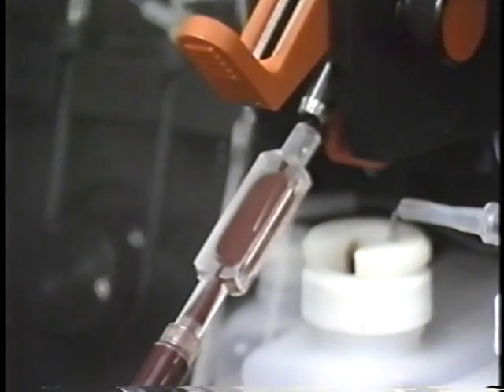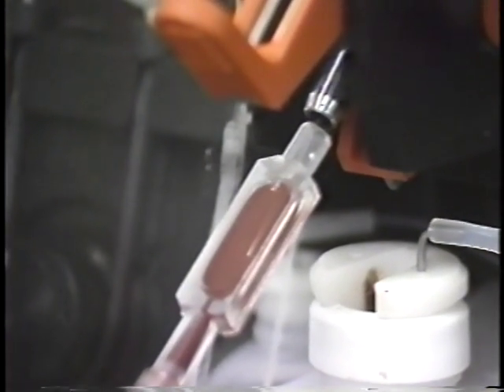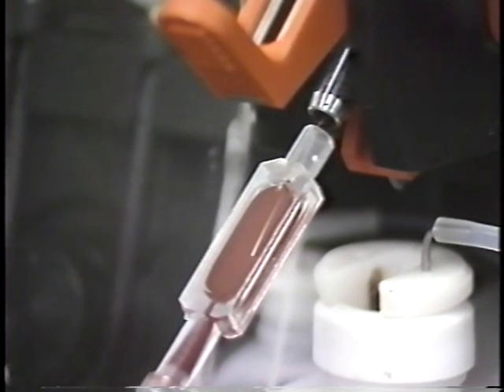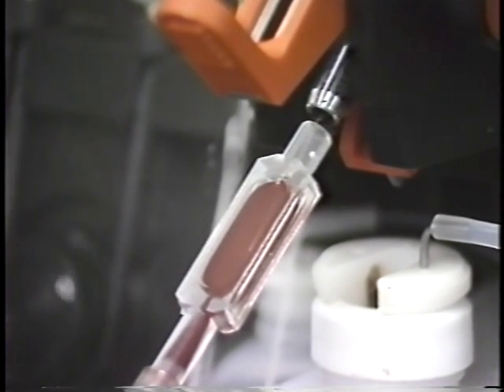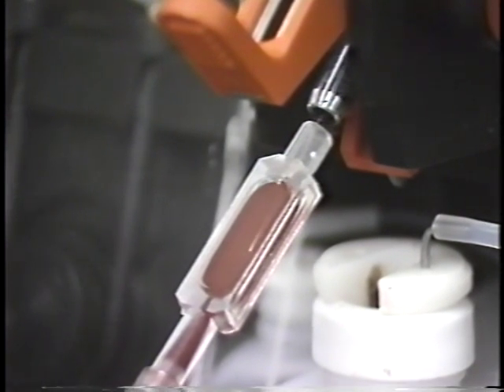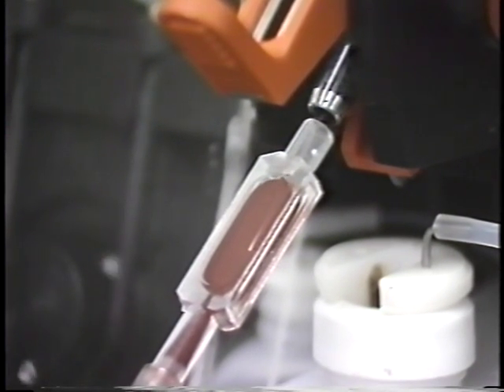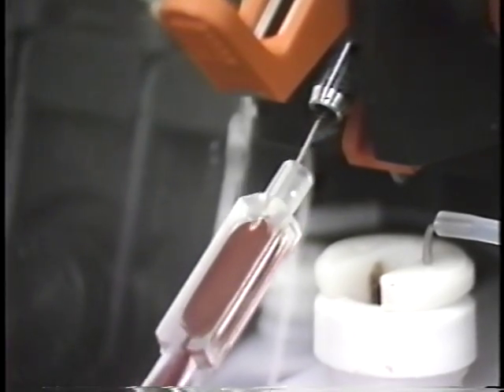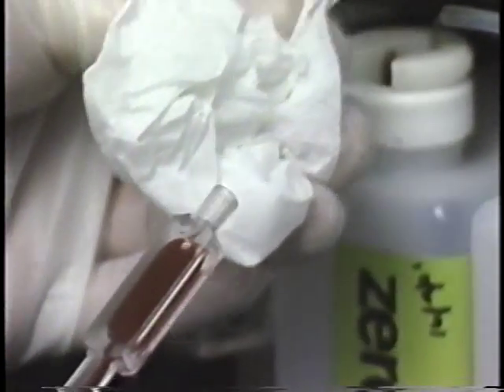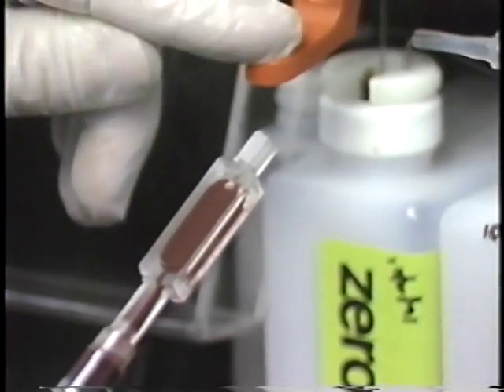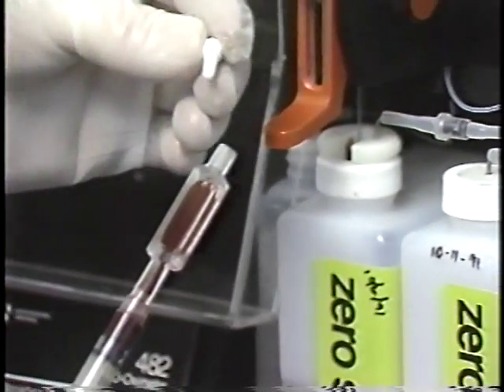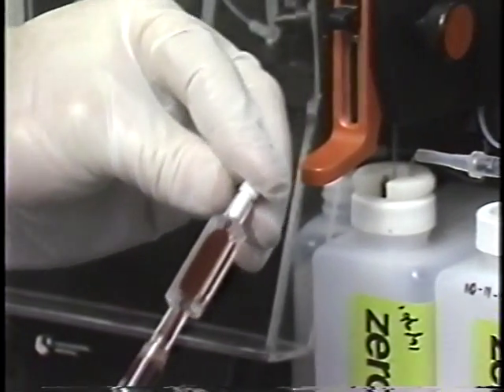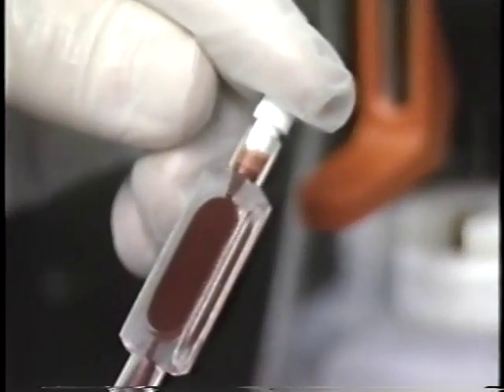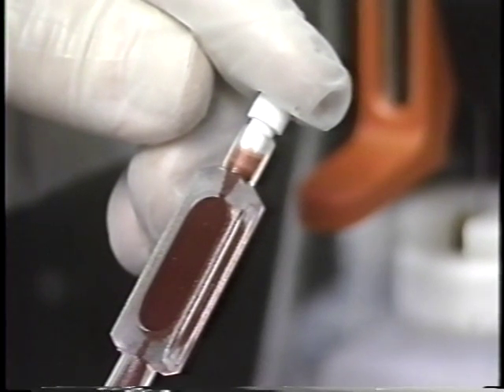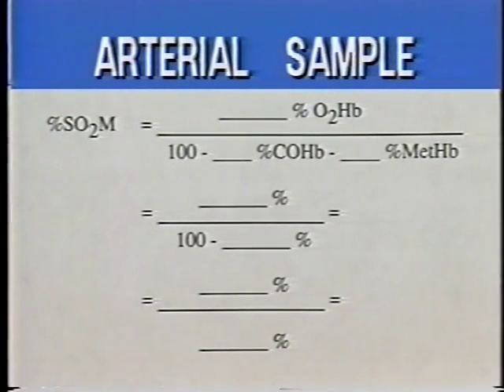To maintain a sufficient level of blood in the cuvette as the co-oximeter is aspirating, slowly inject more blood into the cuvette. Immediately following the completion of the aspiration of the sample by the co-oximeter, place a porous filter in the cuvette and fill the cuvette until the sample permeates the filter and pressure is felt. Now, if necessary, calculate the total oxygen saturation.